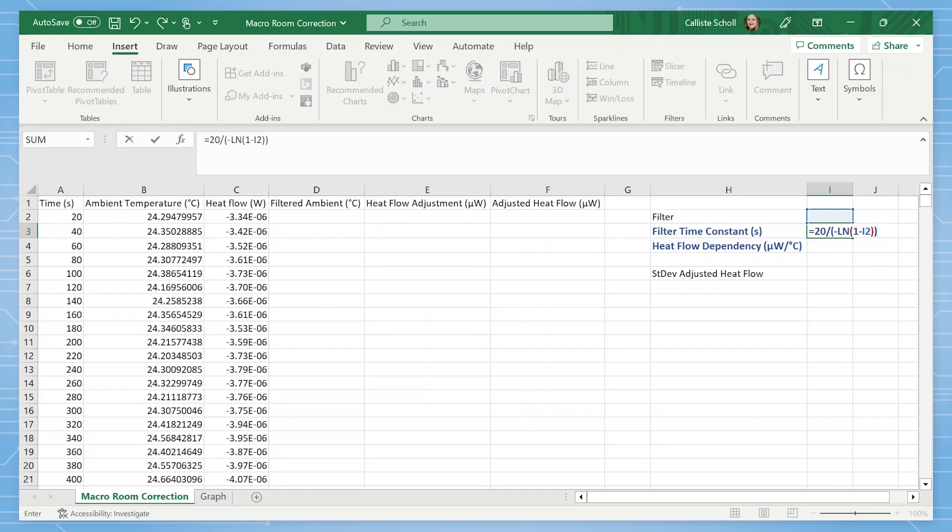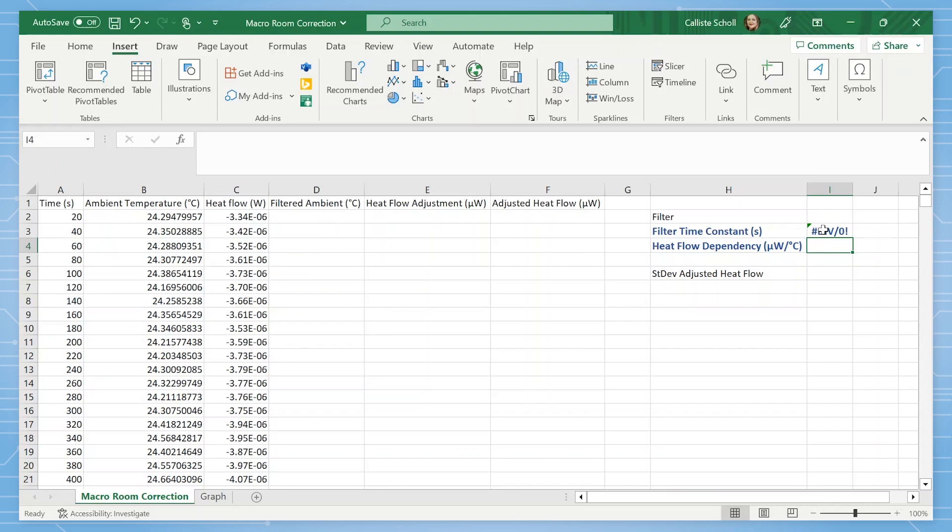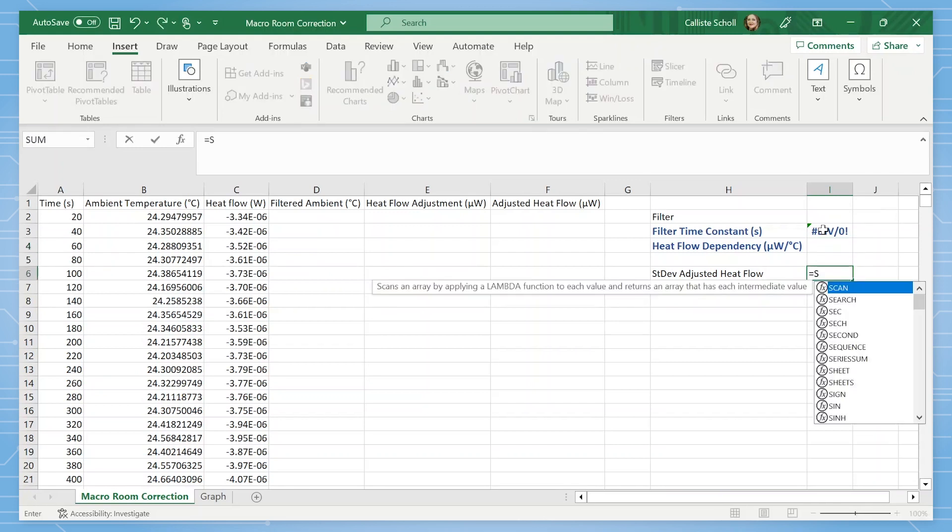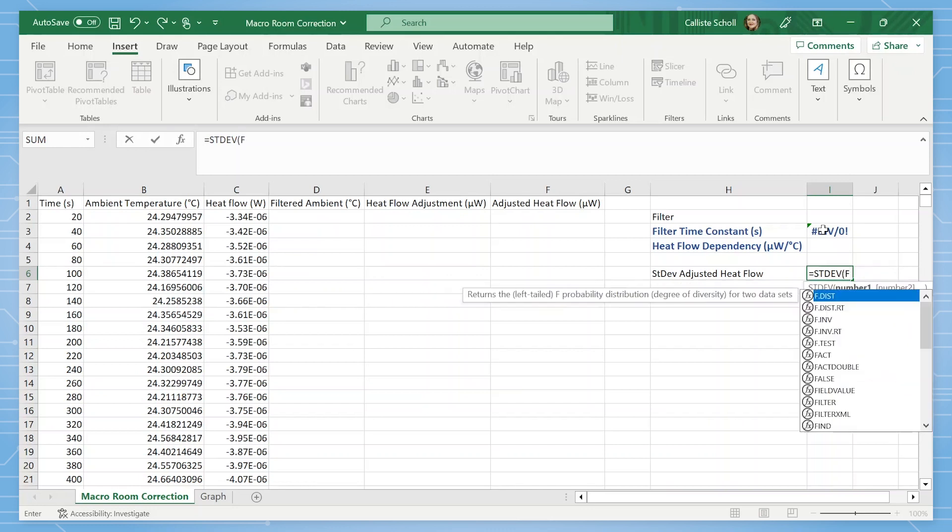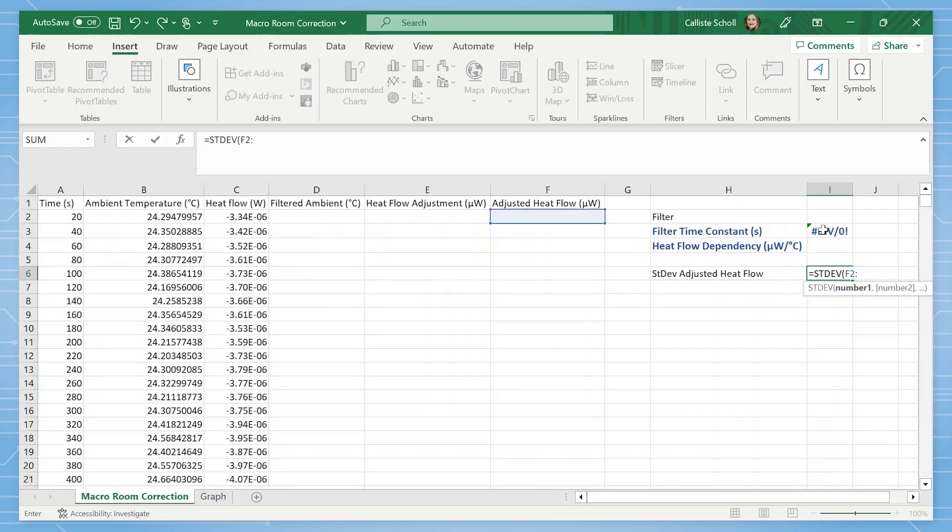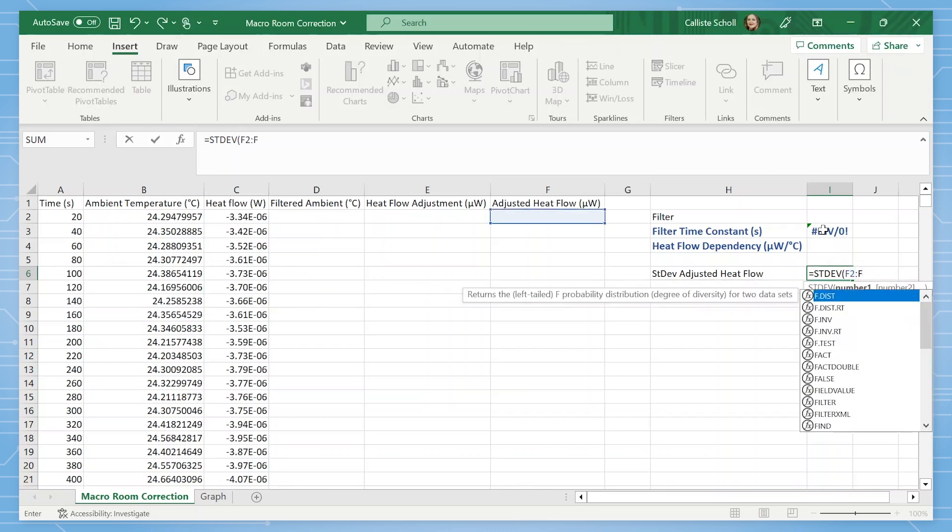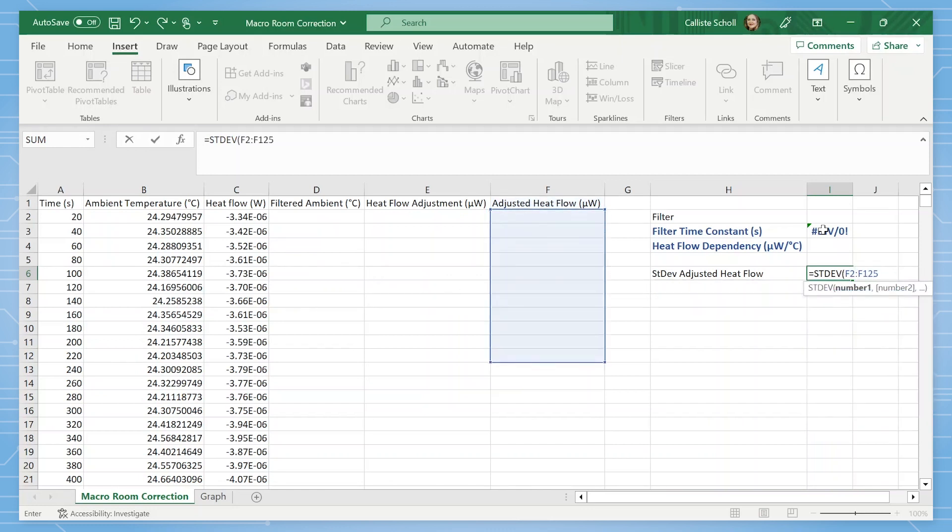The second value we will be solving for is the heat flow dependency, which is the shift in baseline per degree Celsius of ambient temperature change. And finally, the standard deviation of adjusted heat flow signal, which is equal to the standard deviation of the cell range for the adjusted heat flow column.